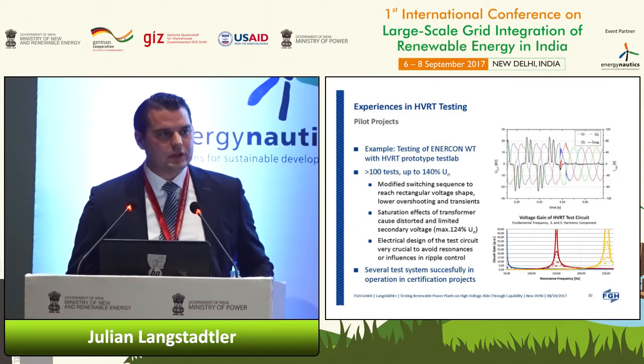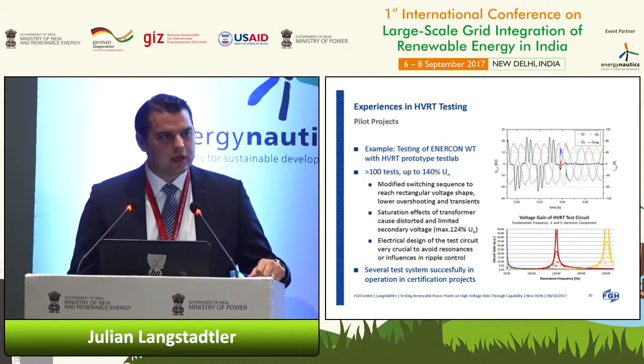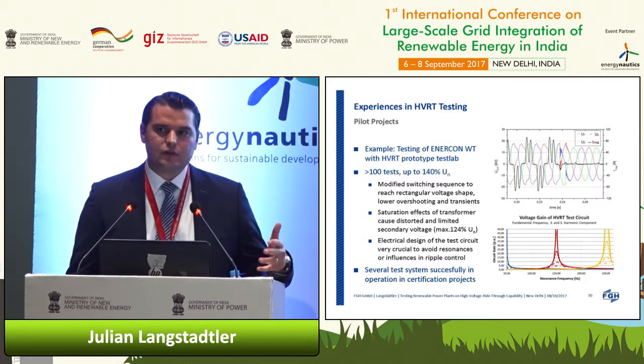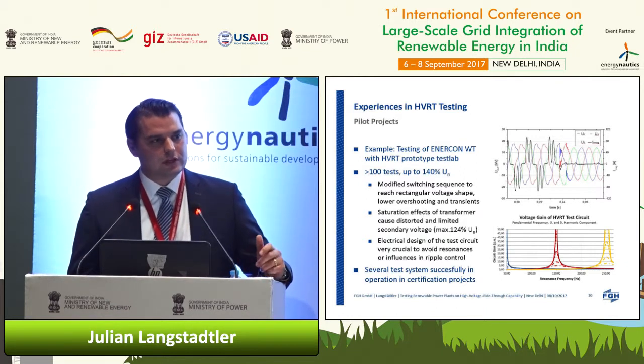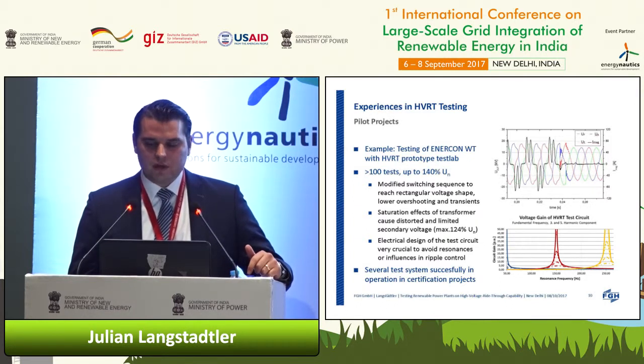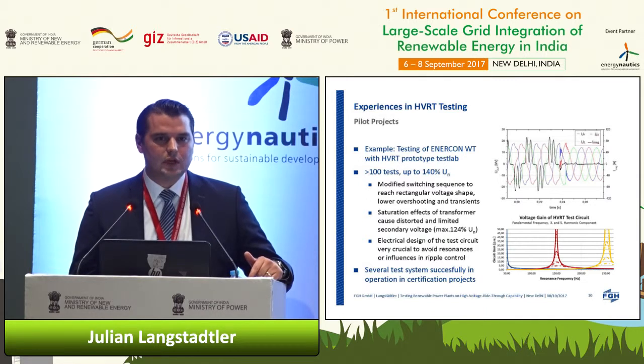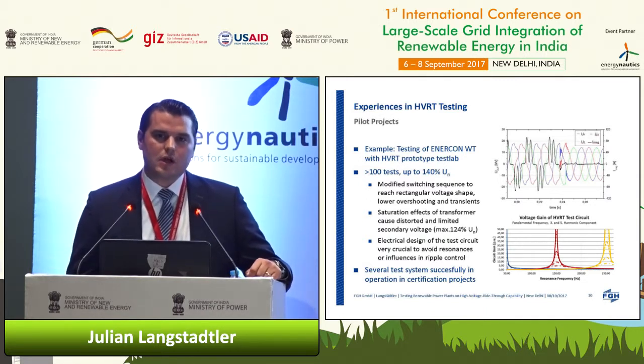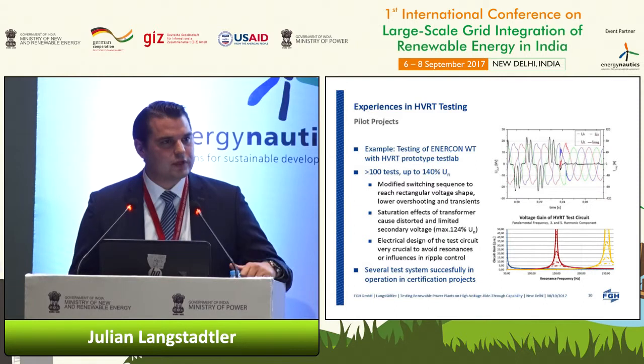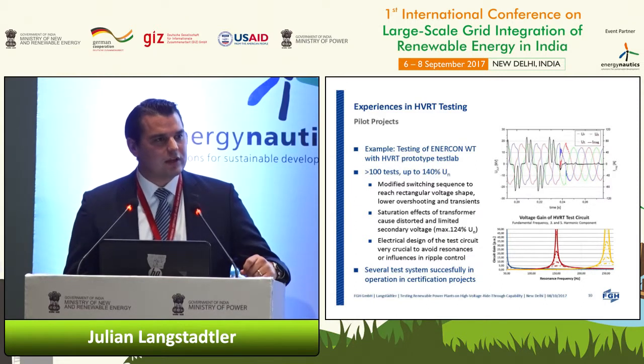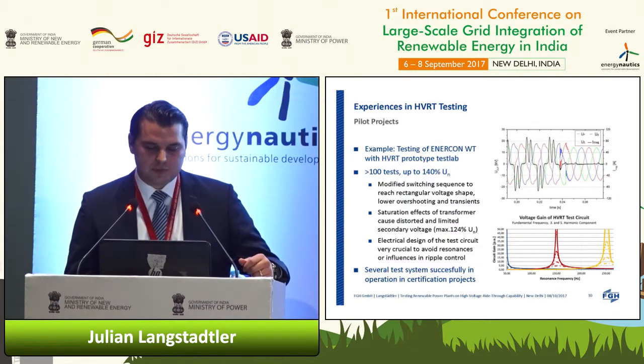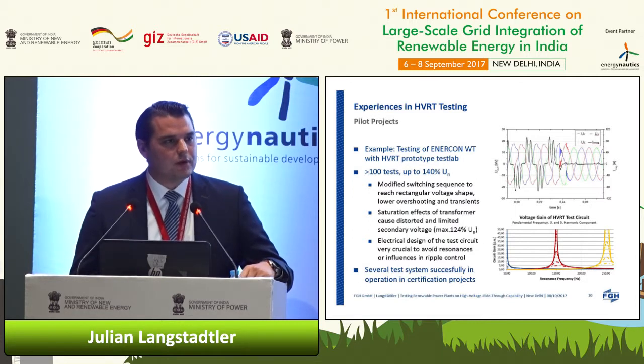On the other hand, you also see in the picture on the right the transformer, which is normally used for solar power plants, but also for wind power plants, where the direct conversion of electricity of the generating unit is on the low voltage side. However, the testing will always be done on the medium voltage side, so there will always be a machine transformer in between. This machine transformer has a saturation, of course, and this saturation on the secondary side limits the overvoltage that comes from the primary side. So whenever you have 170%, for example, on the primary side, it doesn't mean that you will also see 170% on the device under test. It's maybe restricted to only 125%. This should also be taken into account in the development of grid codes.